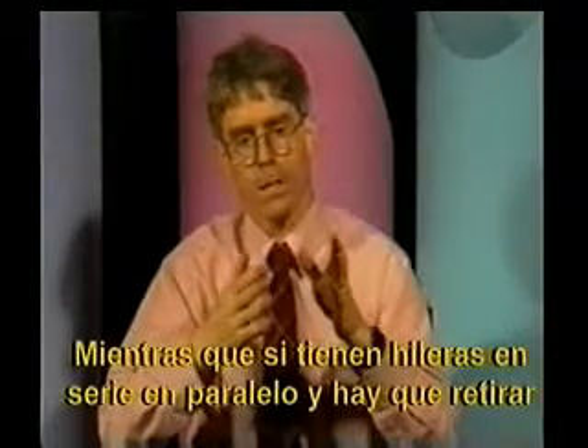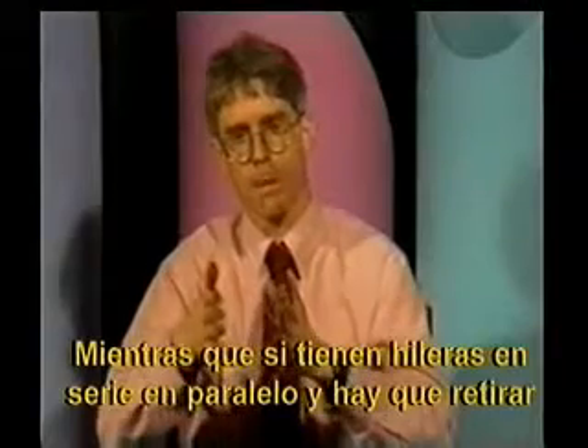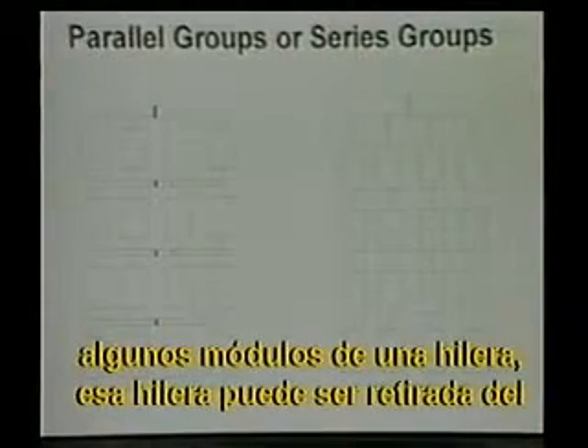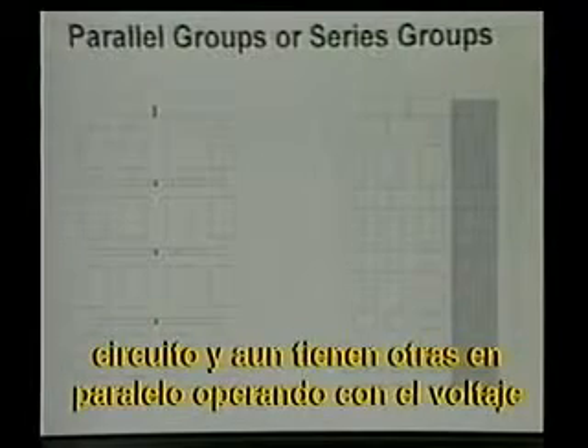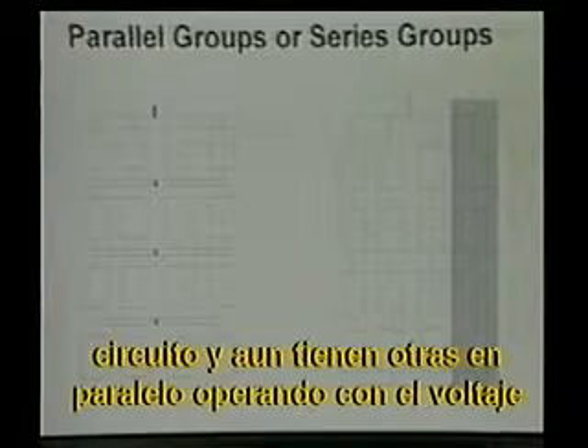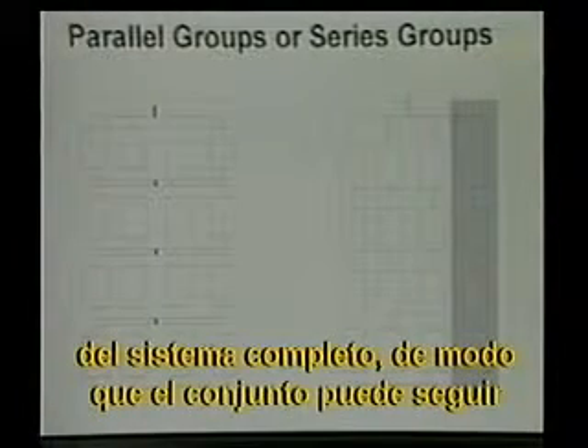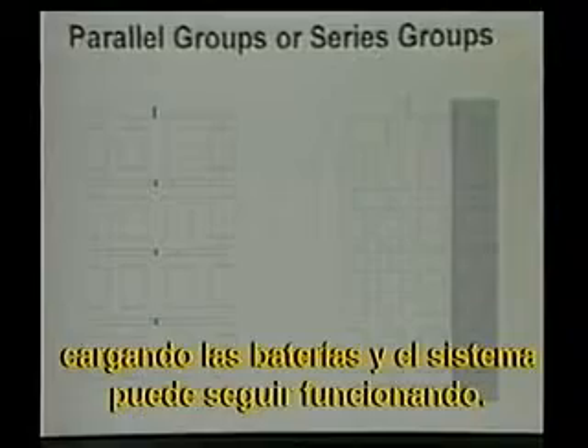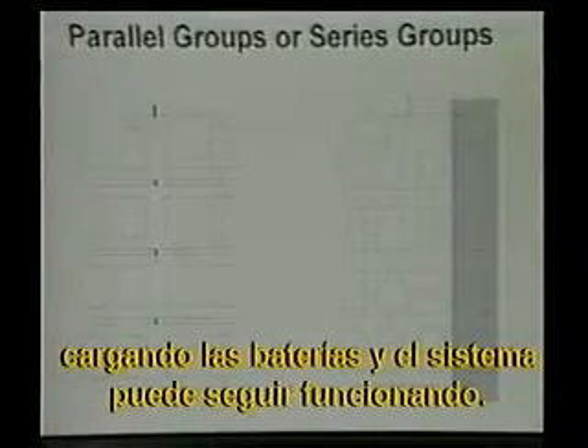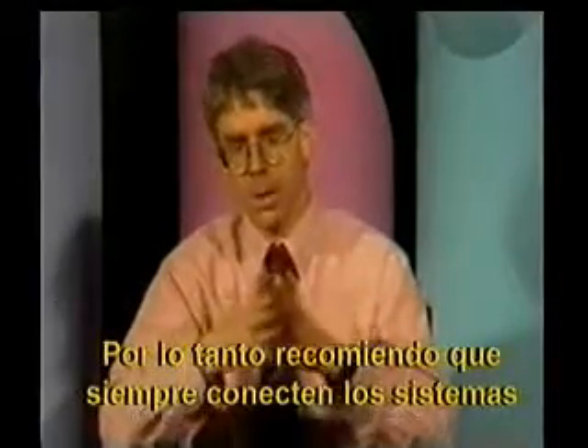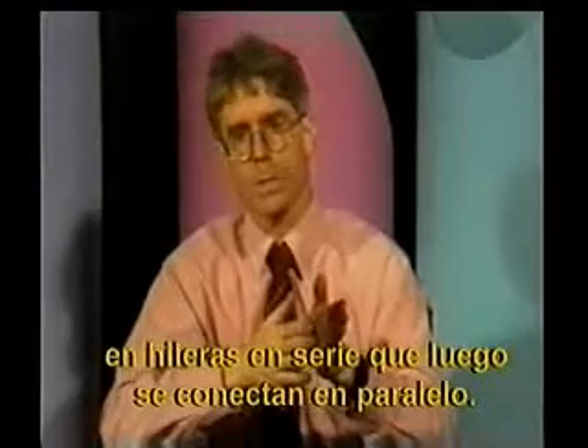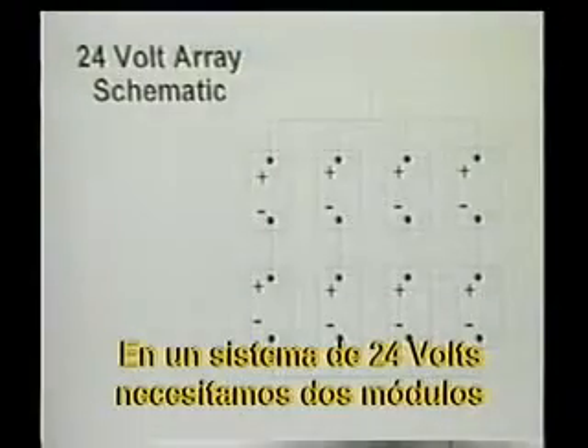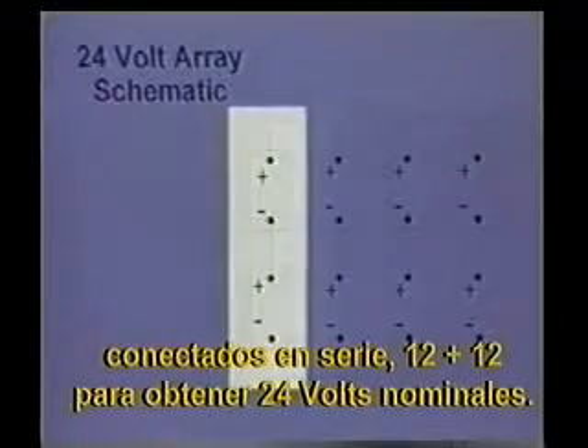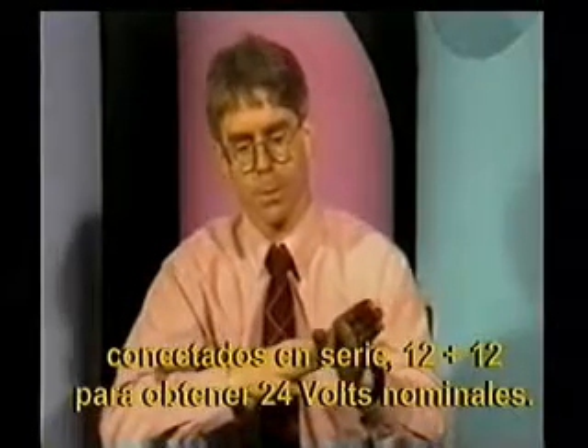Whereas if you have series strings wired in parallel and some modules in one string need to be removed or worked on, that string can be removed out of the circuit and you still have other parallel strings operating at full system voltage. So the array is able to continue to charge your batteries and the system is able to continue operating. So in actual field operation, I recommend always wiring systems in series strings that are then connected in parallel. In the case of a 24-volt system, that means we need two modules wired together in series, 12 plus 12 to give 24 nominal volts.